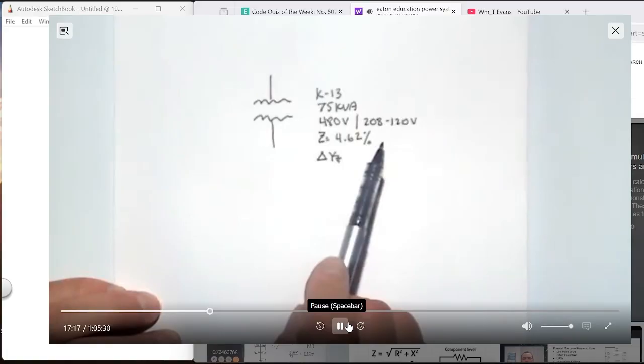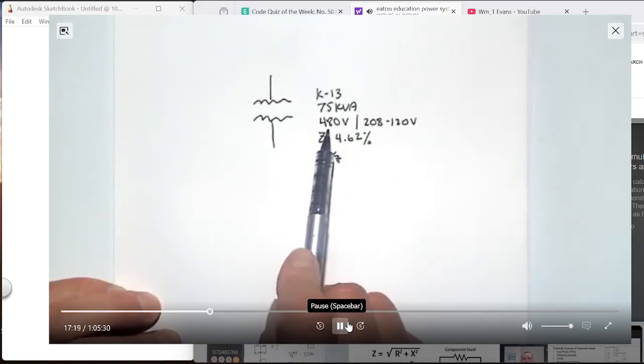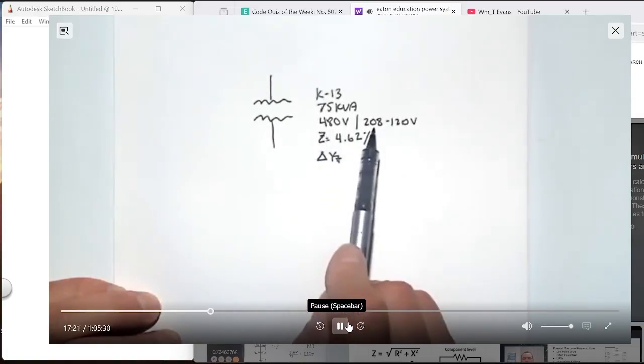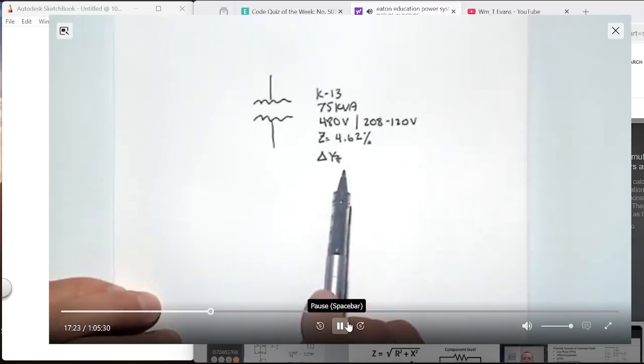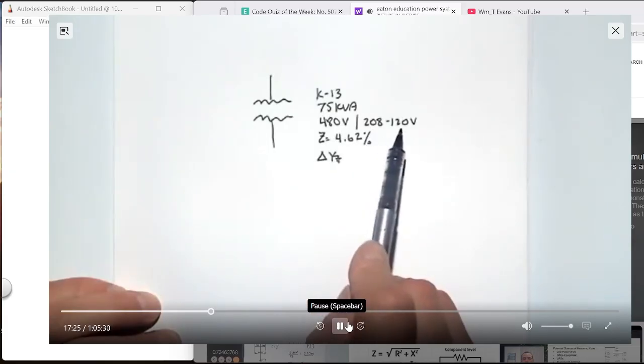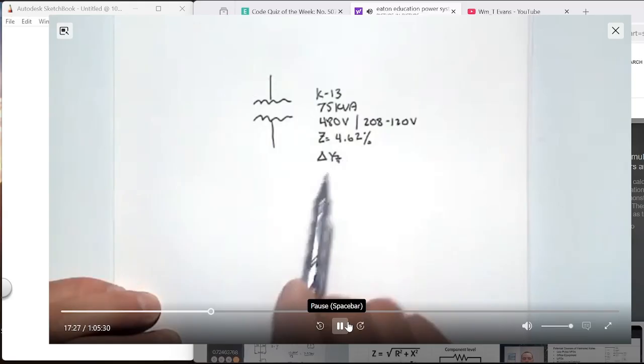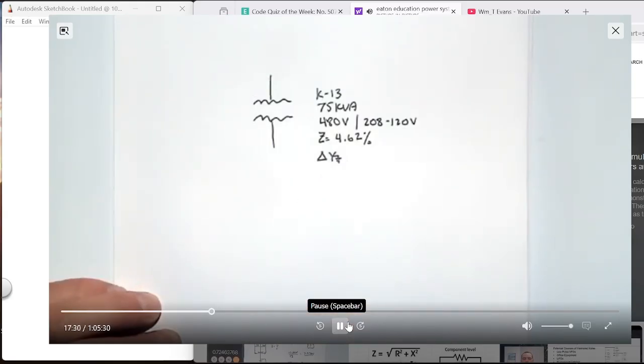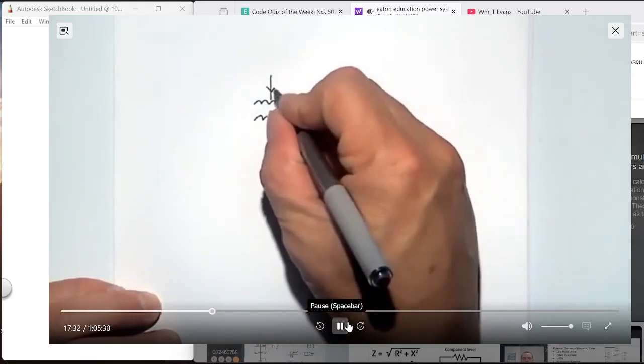480 volt, 208, 120. What does that mean? It's 480 line to line delta on the primary, 208 line to line on the secondary connected in a Y, so 120 line to neutral. And the impedance is 4.62%. So let's calculate I full load primary.